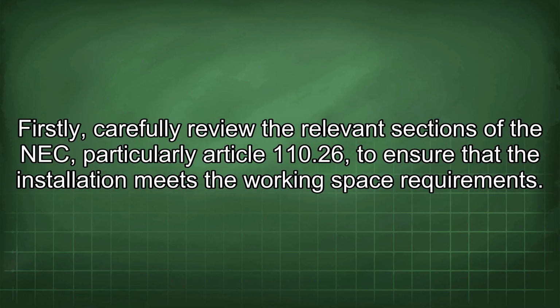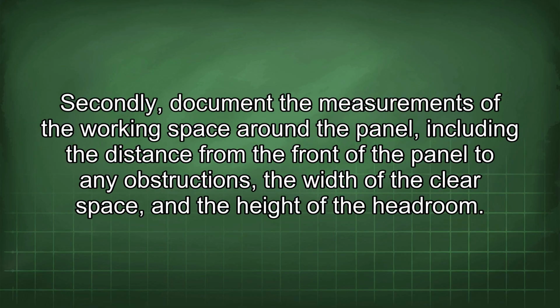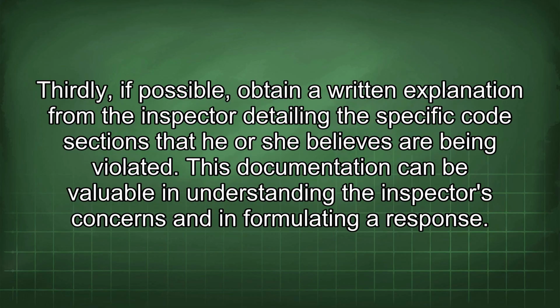Firstly, carefully review the relevant sections of the NEC, particularly Article 110.26, to ensure that the installation meets the working space requirements. Secondly, document the measurements of the working space around the panel, including the distance from the front of the panel to any obstructions, the width of the clear space, and the height of the headroom. Thirdly, if possible, obtain a written explanation from the inspector detailing the specific code sections that he or she believes are being violated. This documentation can be valuable in understanding the inspector's concerns and in formulating a response.